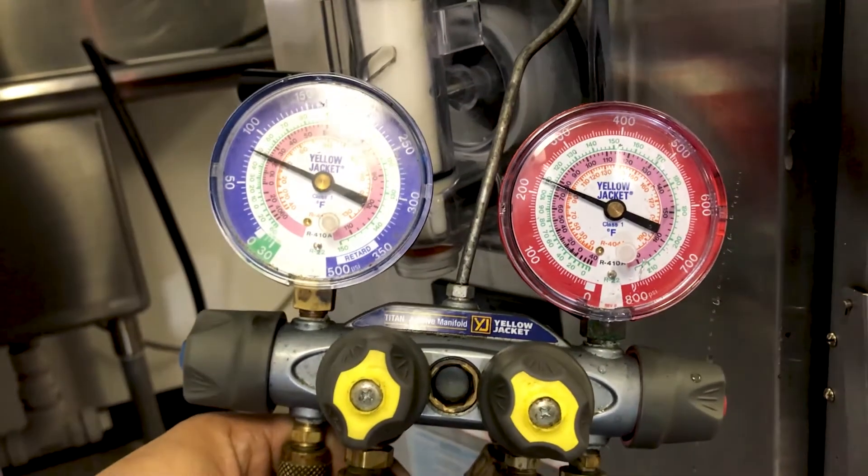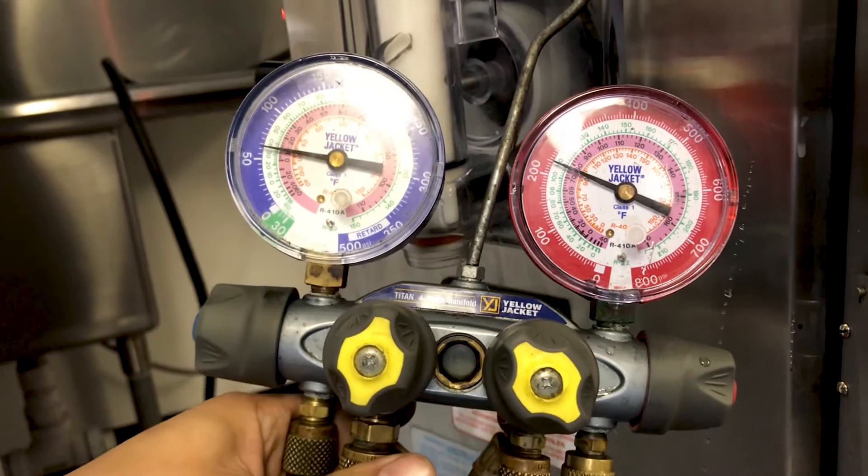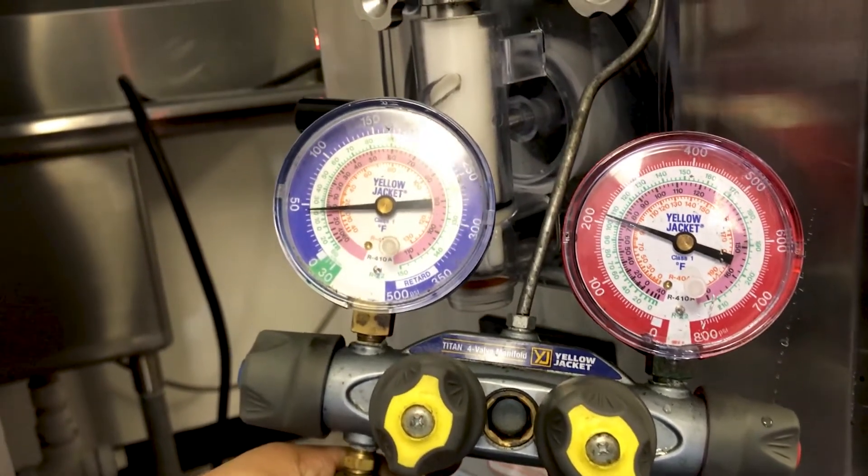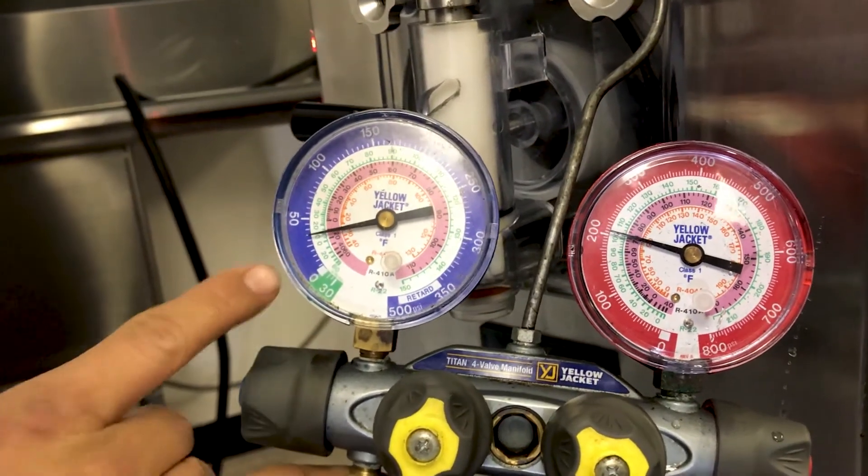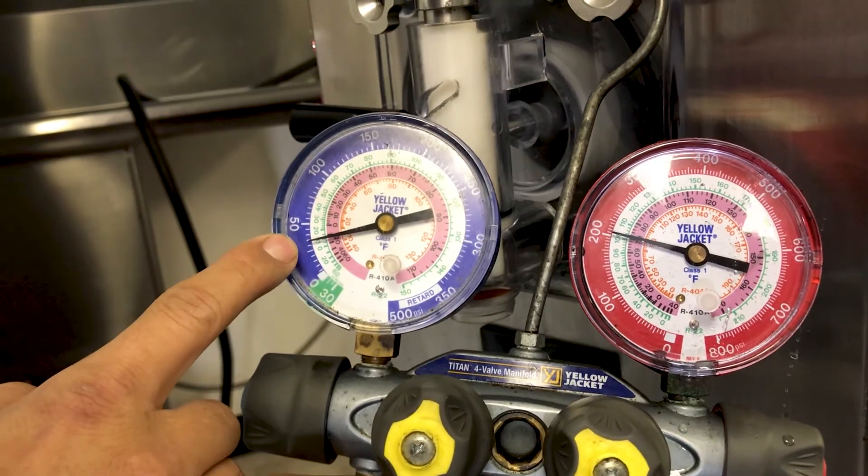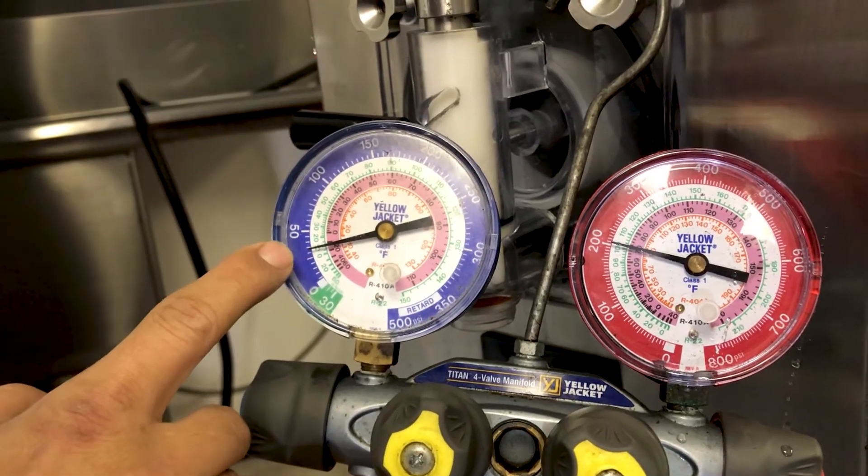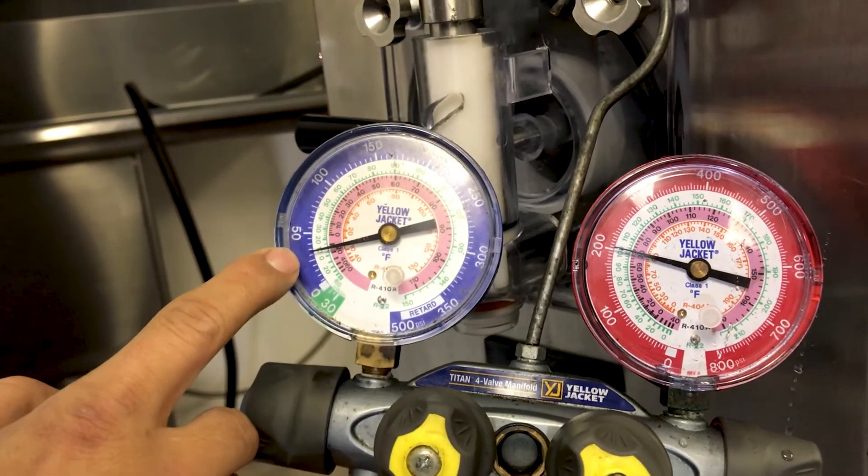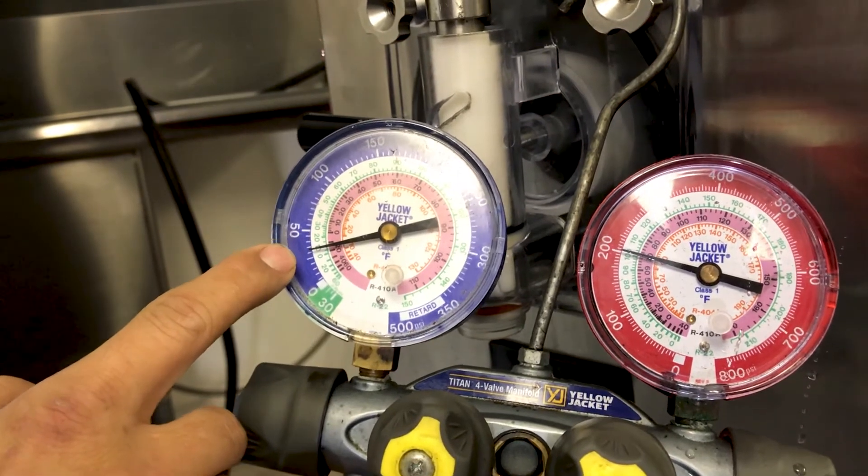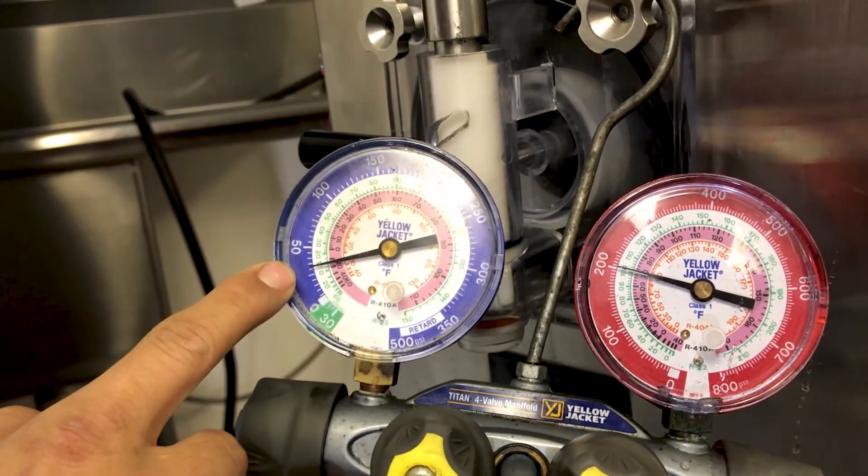So here you're going to see the pressure start getting to where they need to be. And on this particular machine, Taylor recommends the low side to set around 30 to 35. So as you see right here, it's settling right on top of 30, 31 maybe. So that's where we're supposed to be.